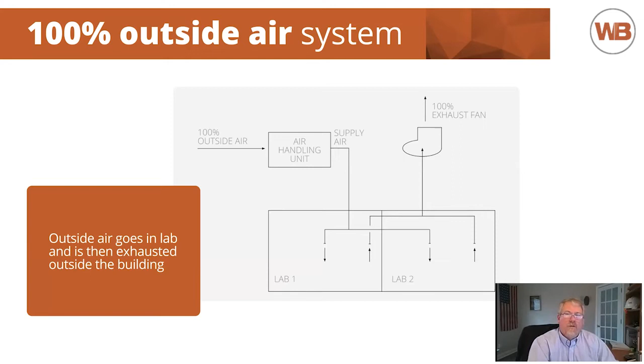The reason this is on the docket is to make sure people understand the difference between 100% outside air and single pass air. It's really important because they get used interchangeably, and it's important to understand why they're different. In a single pass air system, you're mixing the return air and the outside air from spaces like offices and some lab spaces that don't have exhaust requirements or are low toxic level or low biology level labs, then mixing that at the air handling unit and sending it to the lab on the right. That lab is what we'd call a single pass air lab - it goes in one time and directly out of the building.